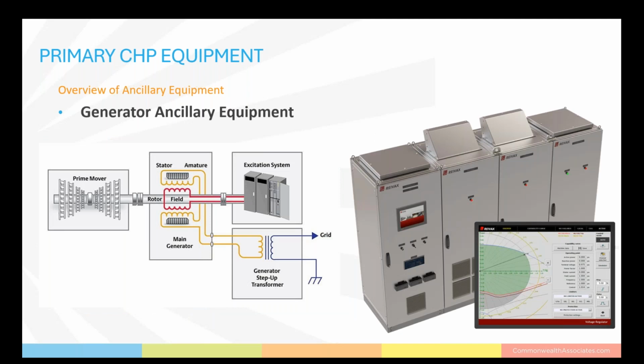Synchronous generators are typically what you see in our designs and require an auxiliary DC voltage excitation system. The DC excitation system has two different designs, rotating and static. The rotating designs are built into the generator, require an AC aux power feed, one or two smaller cabinets that are roughly 2 foot by 3 foot, and a small voltage regulator that's typically 1 or 2 small cabinets. The static design requires several large standalone cabinets. Those are roughly 4 feet by 4 feet, and they can be as tall as 8 feet.